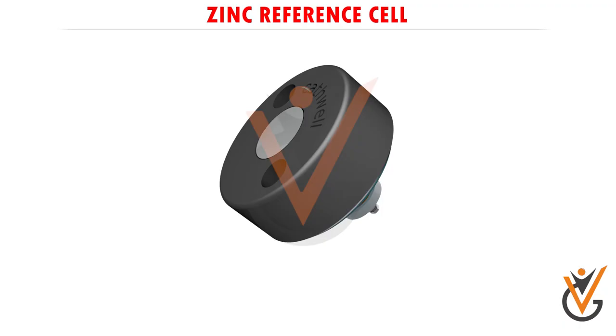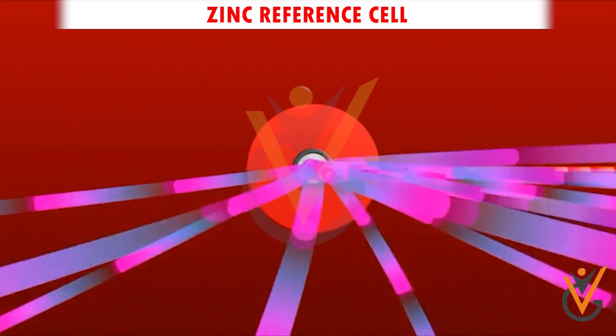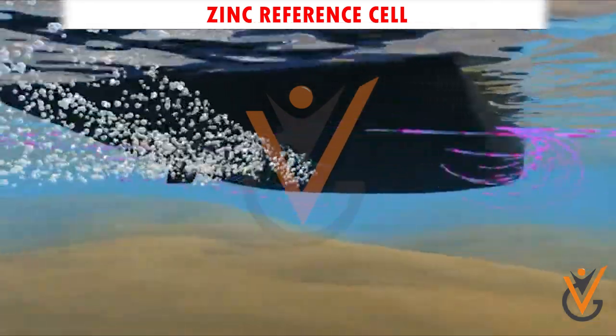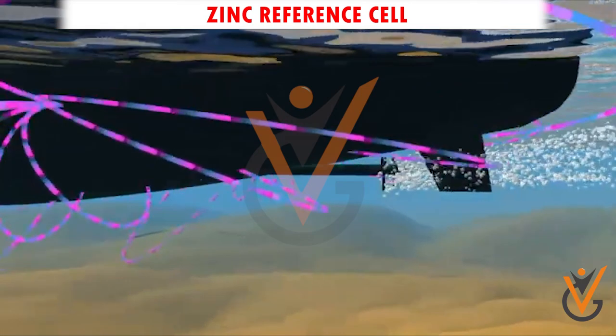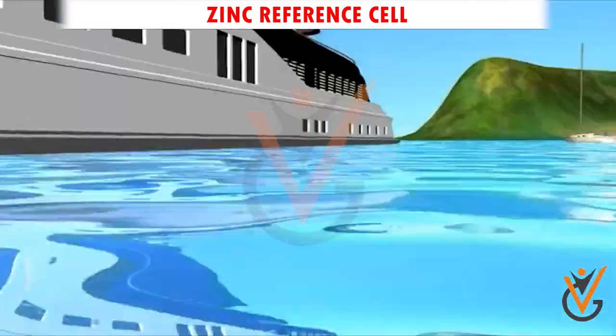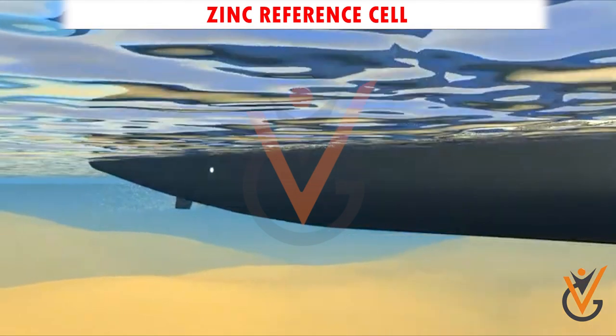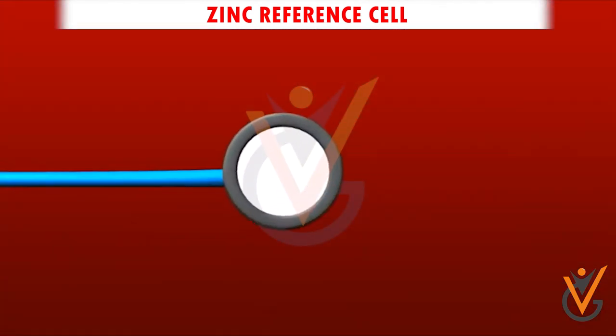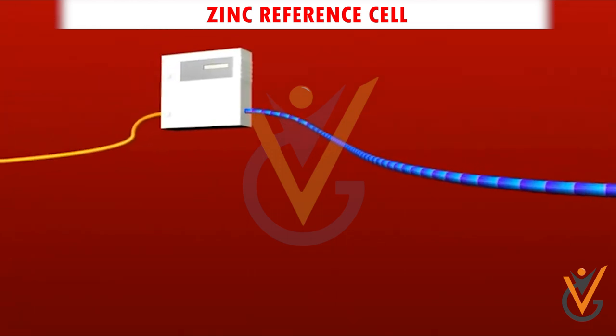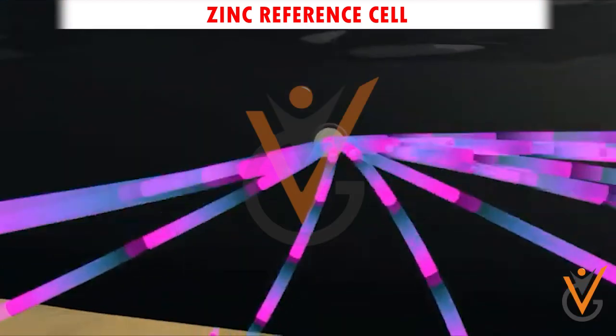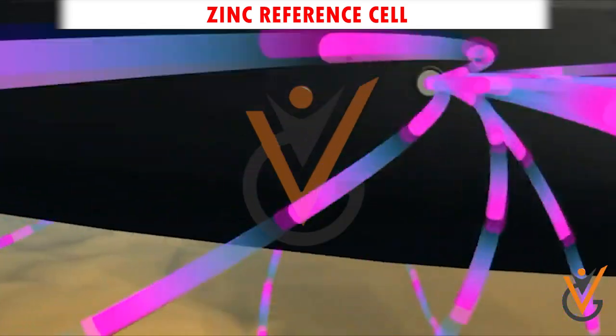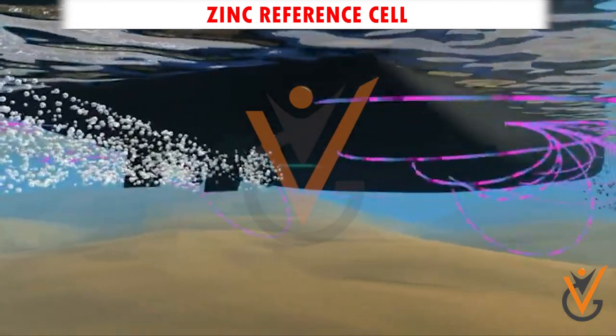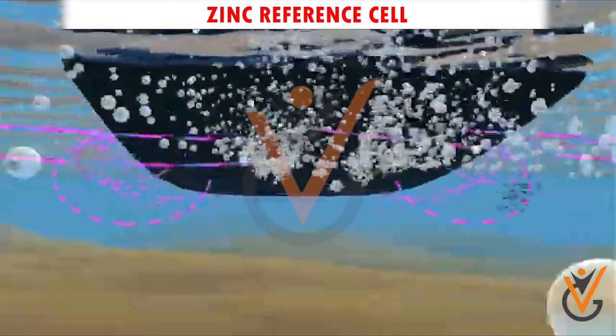Zinc reference cell. The electrical potential is monitored by a reference electrode assembly, which is fitted port and starboard between the anodes, where the lowest possible potential is likely to occur so as to detect the slightest of corrosion currents between the hull and seawater. This reading is fed back to the control panel, which automatically adjusts the impressed current anode output. They are connected through cable lugs and gaskets, and are bolted through a cofferdam body onto the hull surface. These zinc reference cells are highly stable in nature and give a steady reference in which hull and sea potentials can be measured along with small current flows in the system. These electrodes are completely diver-changeable.